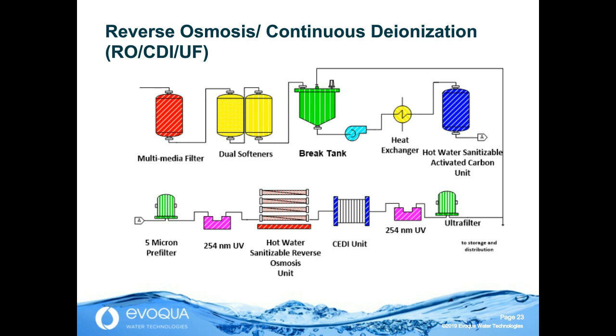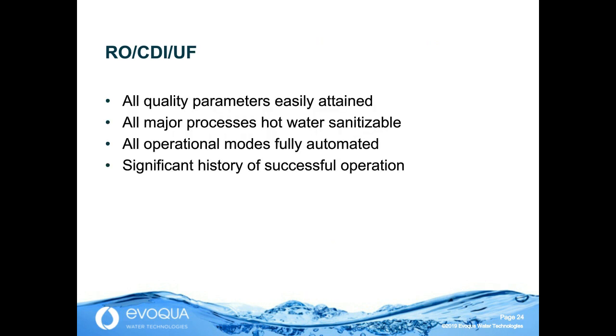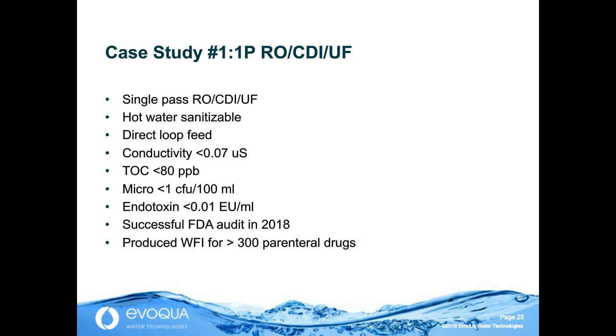All of the critical quality attributes are easily attained. The whole system can be hot water sanitized. All the operational modes are automated, and there is a significant history to go back to. The first case study is a fairly recent single-pass RO, continuous deionization, ultrafiltration, hot water sanitizable, a direct feed to the loop and the use points. The water consumption is well understood, and storage is not needed.